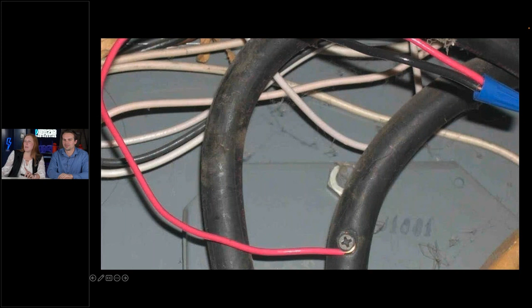At least they've got the local disconnect up there, but they have copper exposed, and there's a little wire nut. It's unbelievable. That's exposed energized parts, because that screw also isn't supposed to be there anyway, and it's resting up against the back of that panel. If that screw goes all the way through, guess what, the panel's energized now. There are all sorts of reasons not to do this, and yet we see it happen.